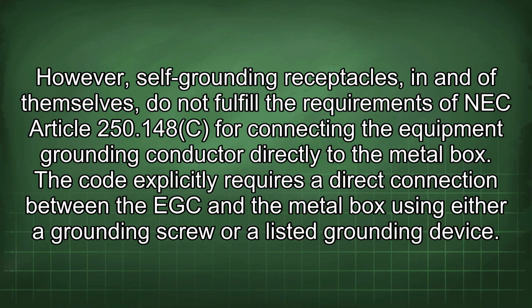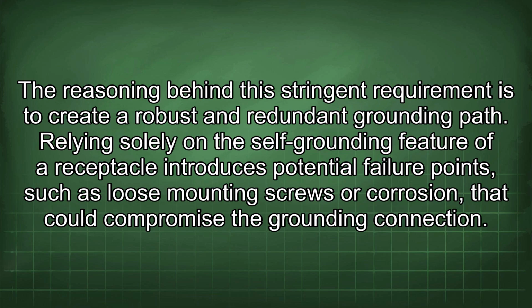The code explicitly requires a direct connection between the EGC and the metal box using either a grounding screw or a listed grounding device. The reasoning behind this stringent requirement is to create a robust and redundant grounding path. Relying solely on the self-grounding feature of a receptacle introduces potential failure points such as loose mounting screws or corrosion that could compromise the grounding connection.